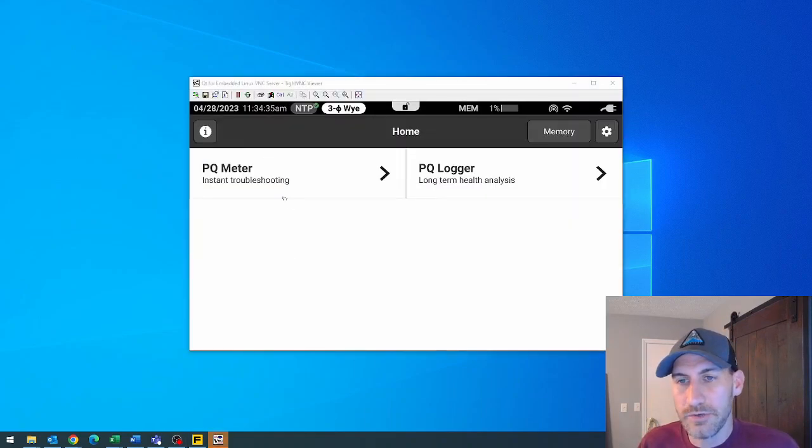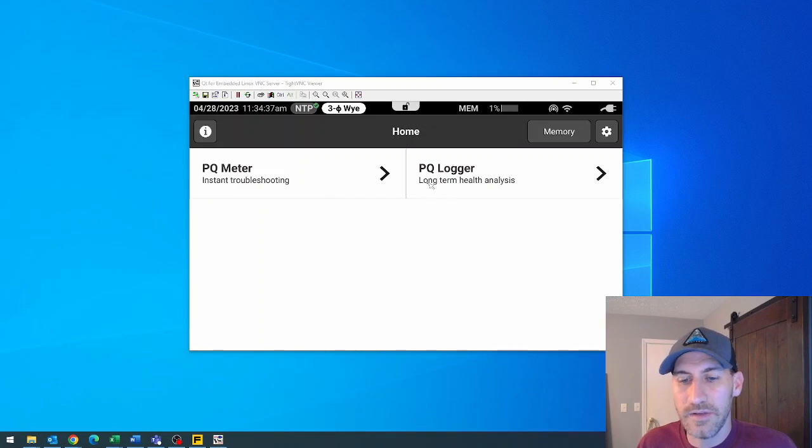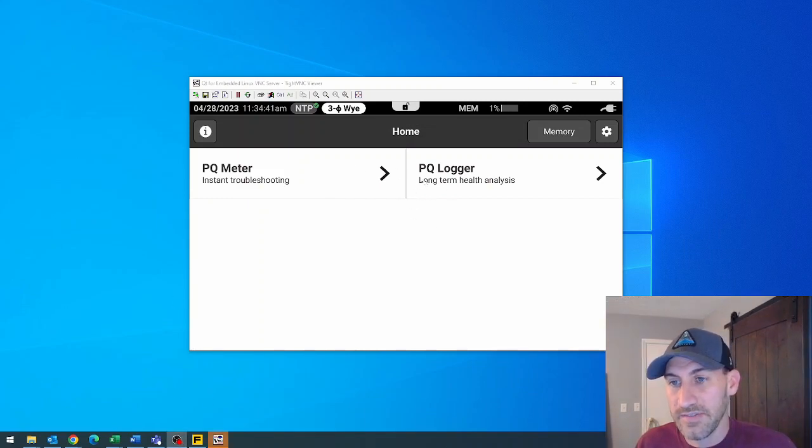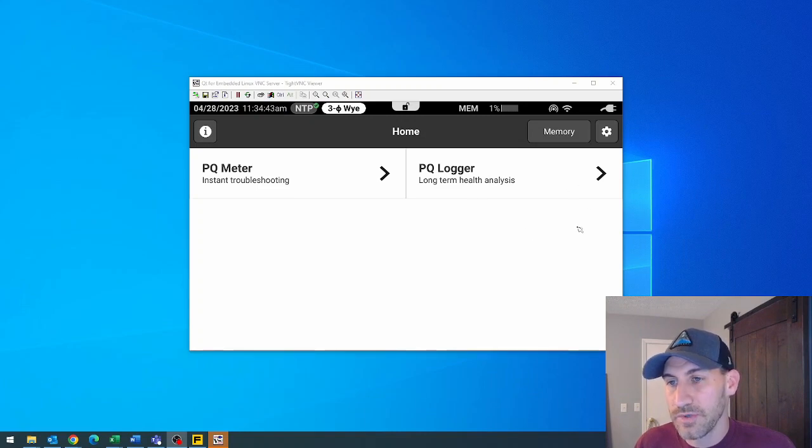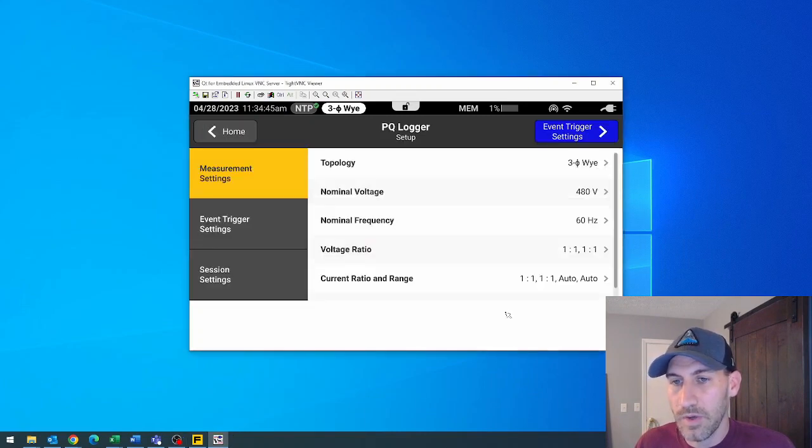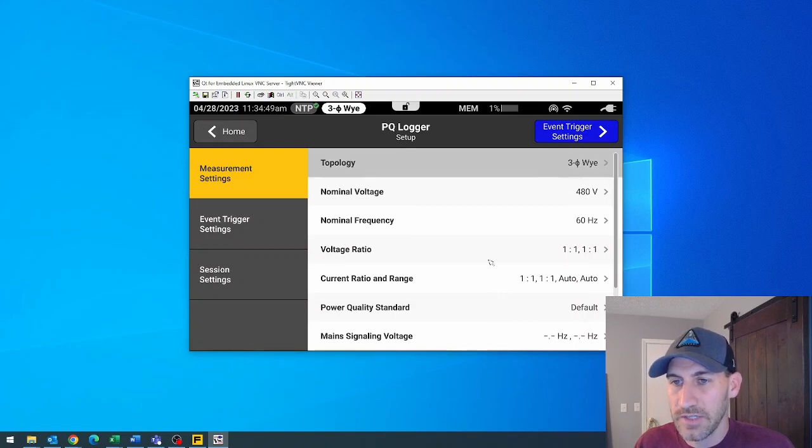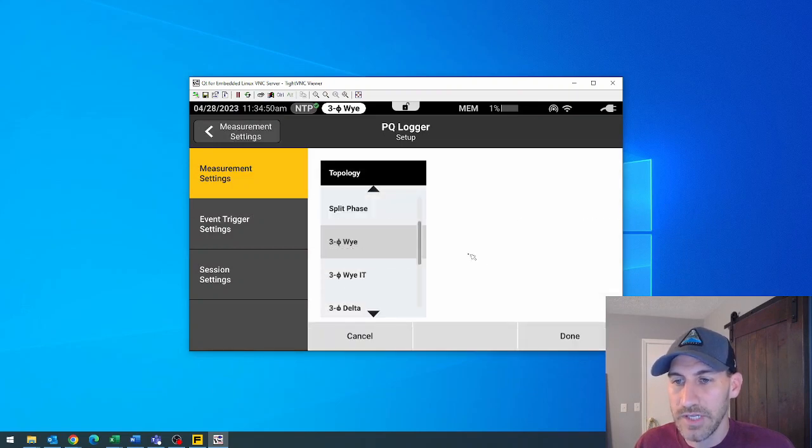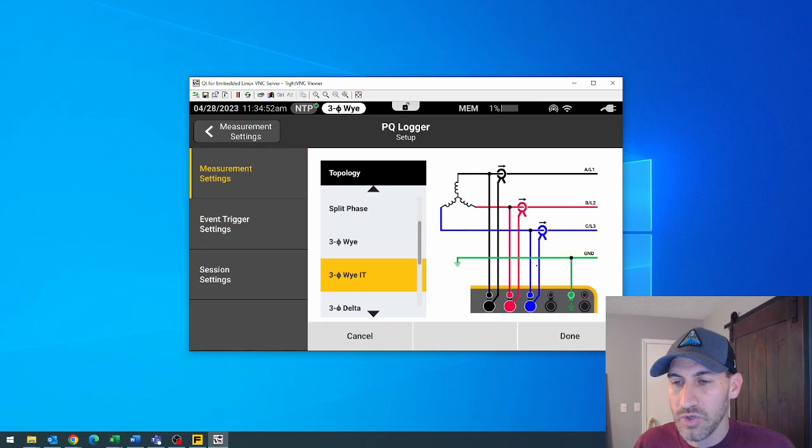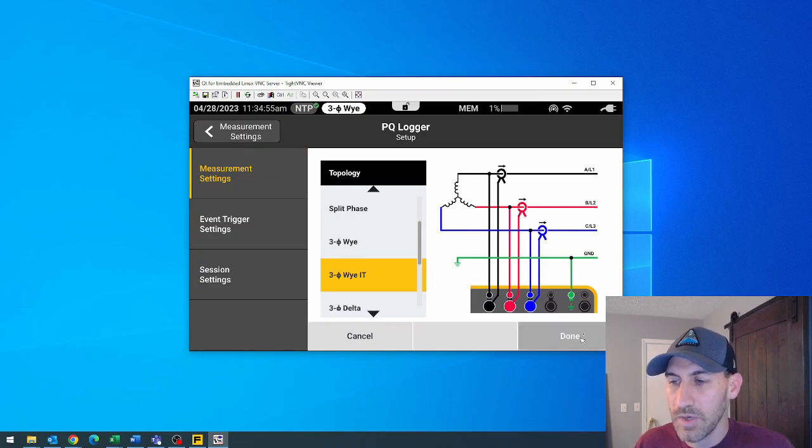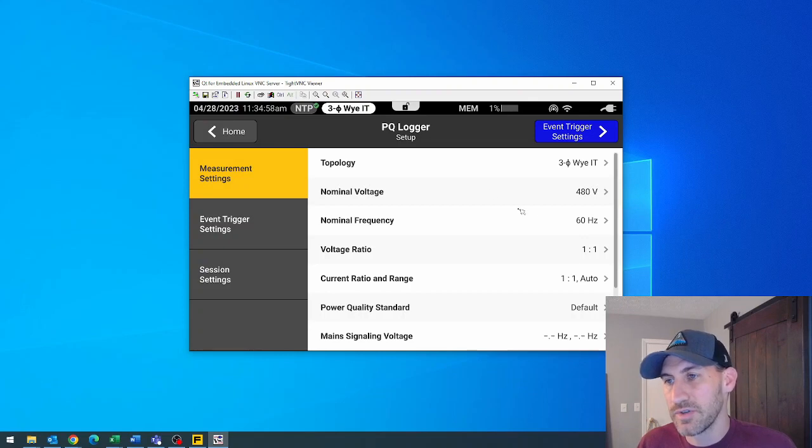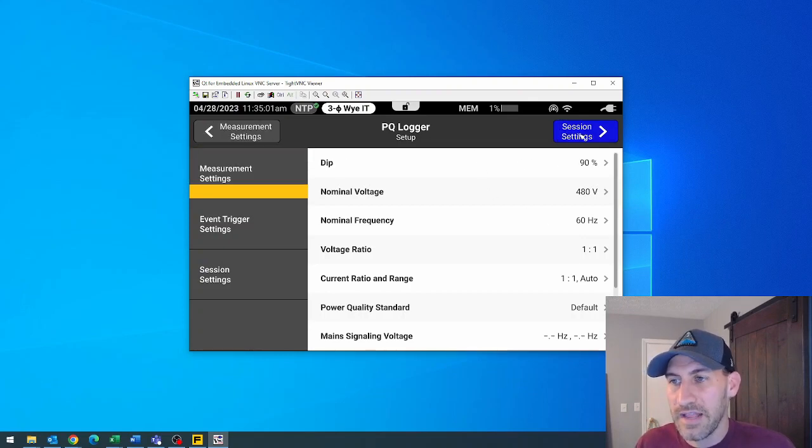Now it's going to show us the screenshot of the VNC at, or of the 1770 series. Just like you were using your touch. You just use your mouse. You click power quality log. It goes to the next screen. You can change your topology or whatever. So I'm controlling this remotely. You can do everything that you would want to on here, just as though you were actually using your finger in front of the device.